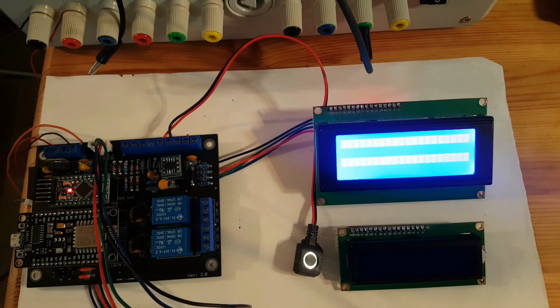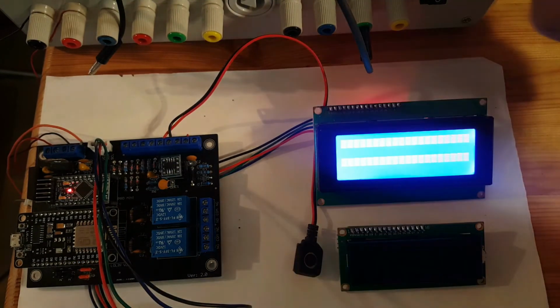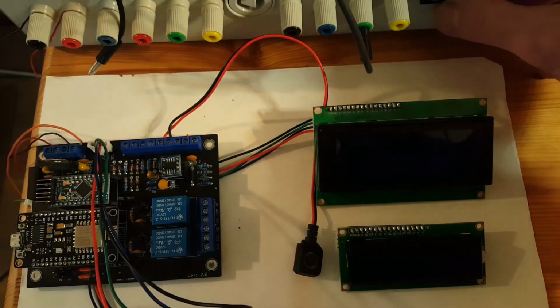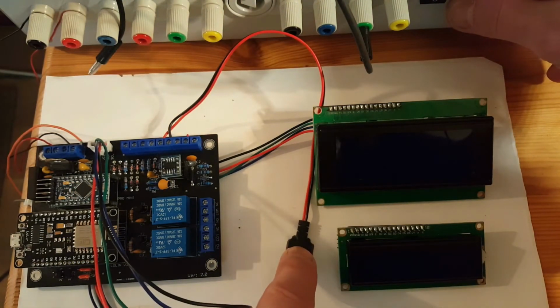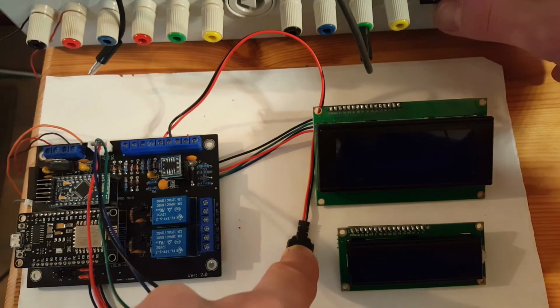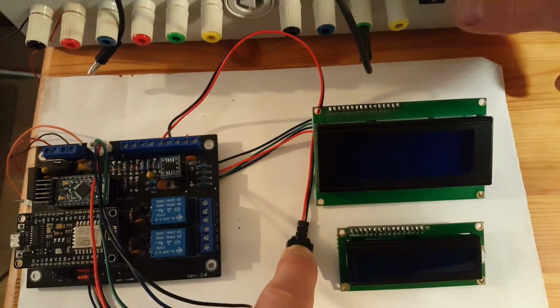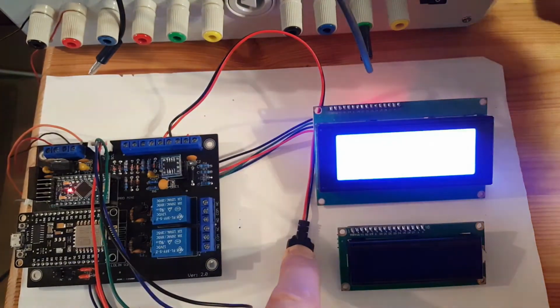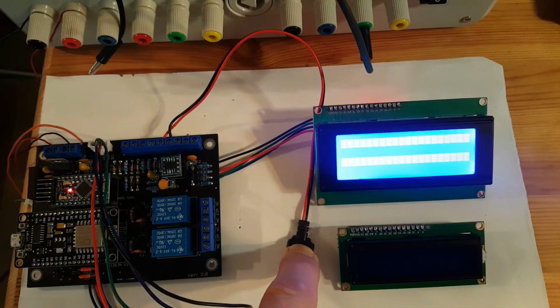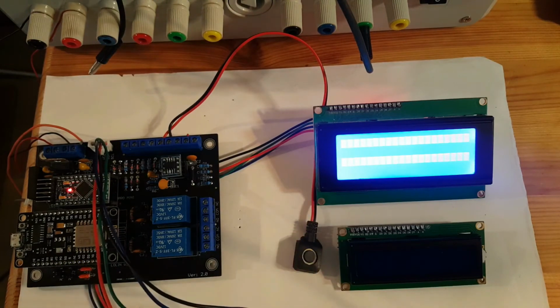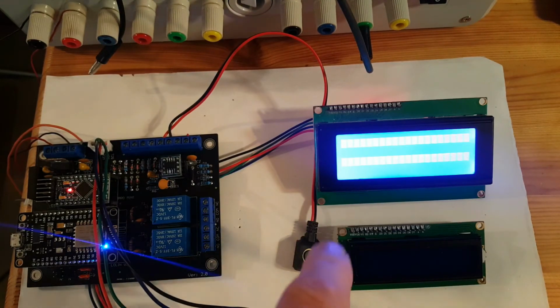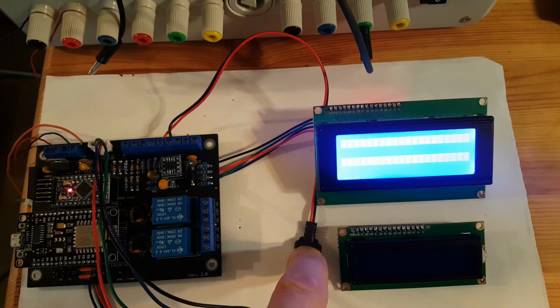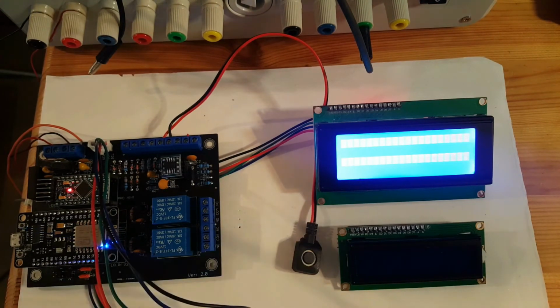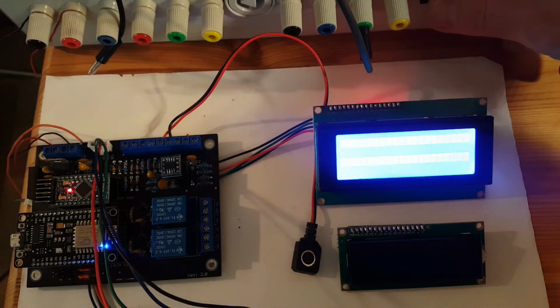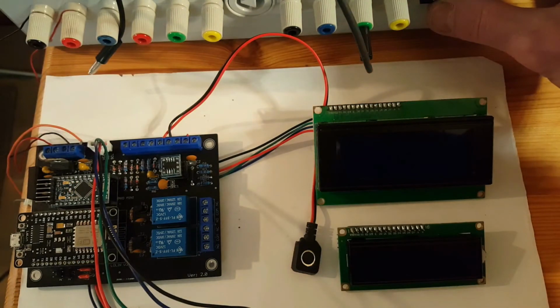Let me show you. So first, what you need to do is to power your EVSE off. Press the button and keep it pressed. Now power your EVSE on and keep the button pressed for about 5 seconds. Then release it and press it again for 4 seconds, and then release it again, switch the power off, and switch power back on again. And now you should see the working screen.